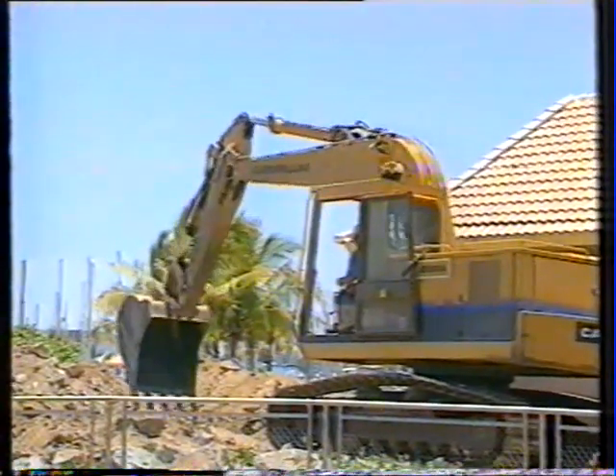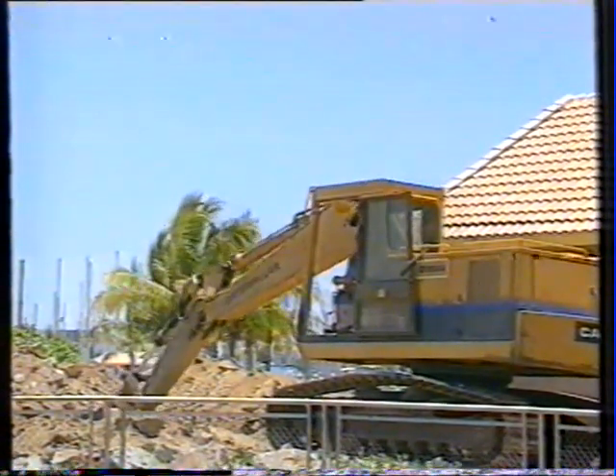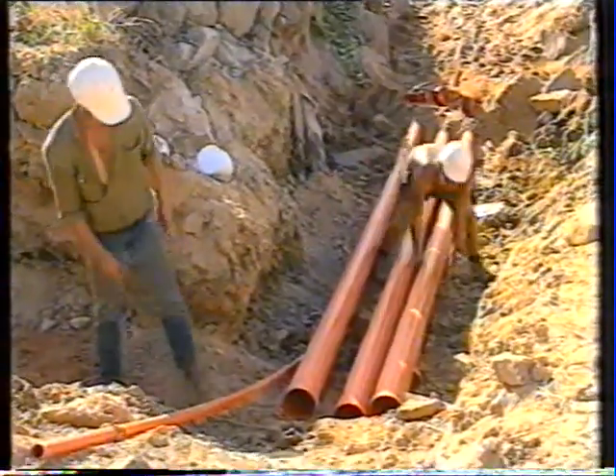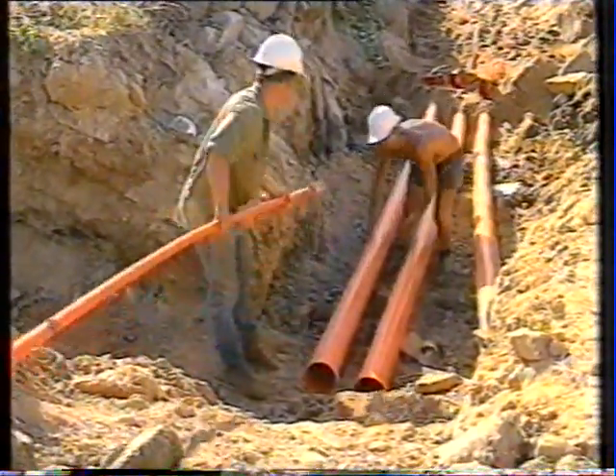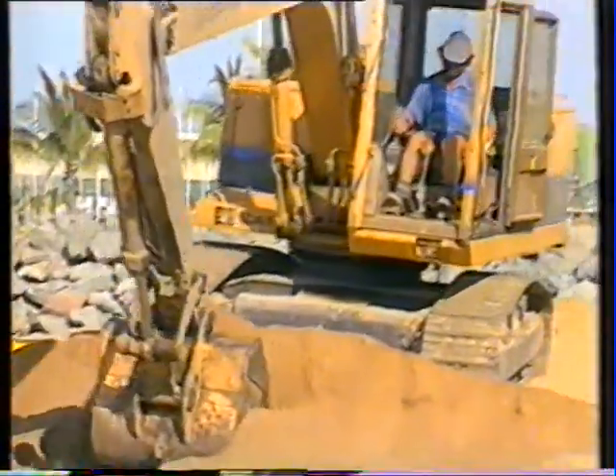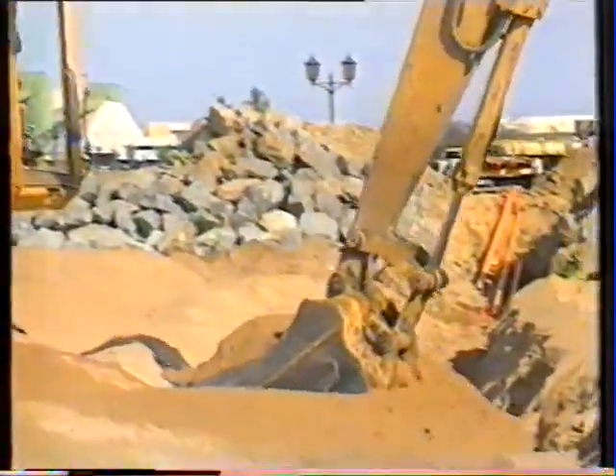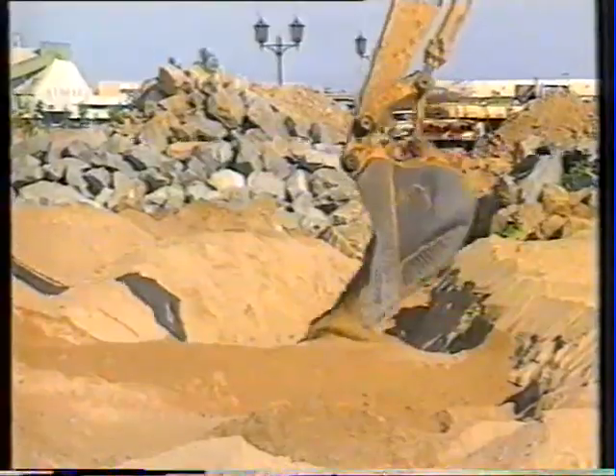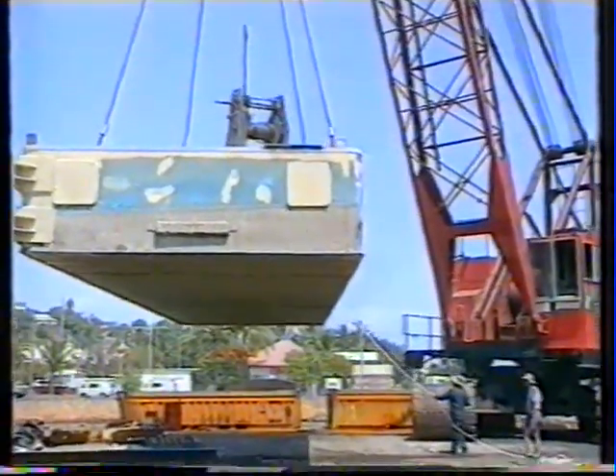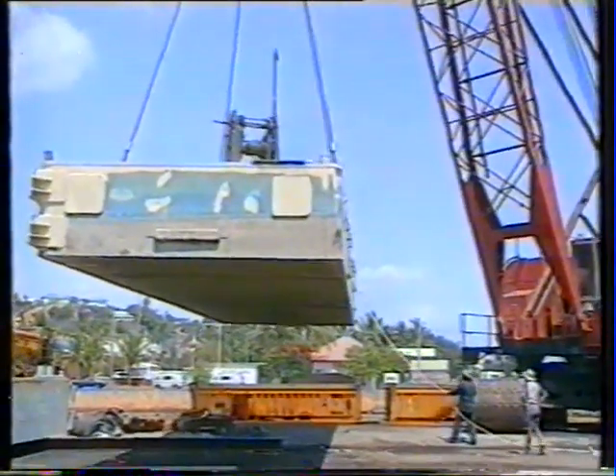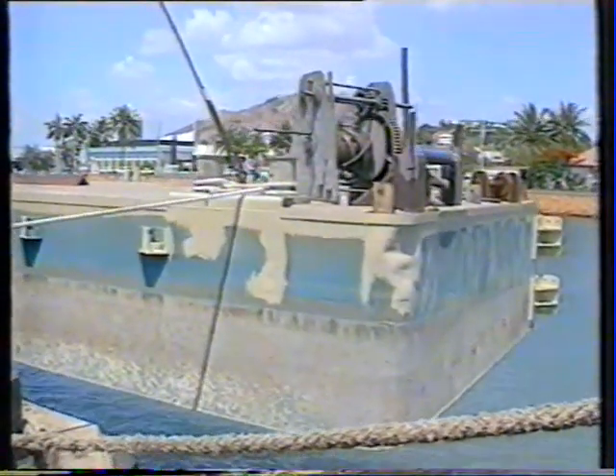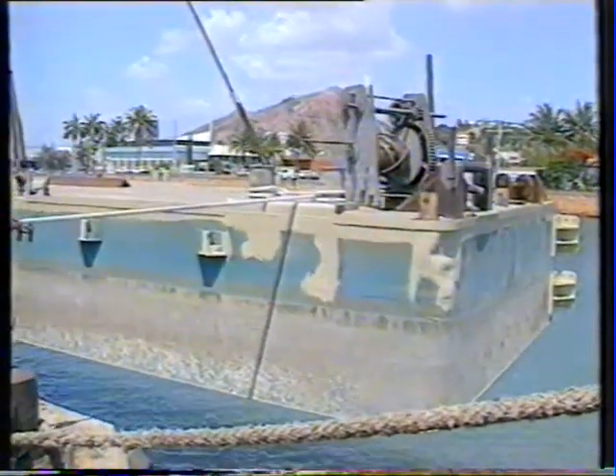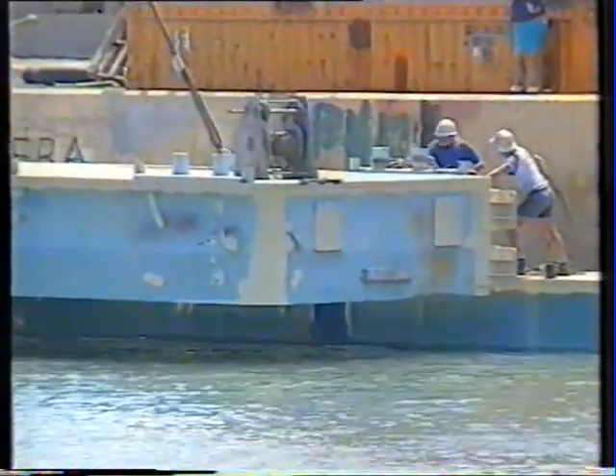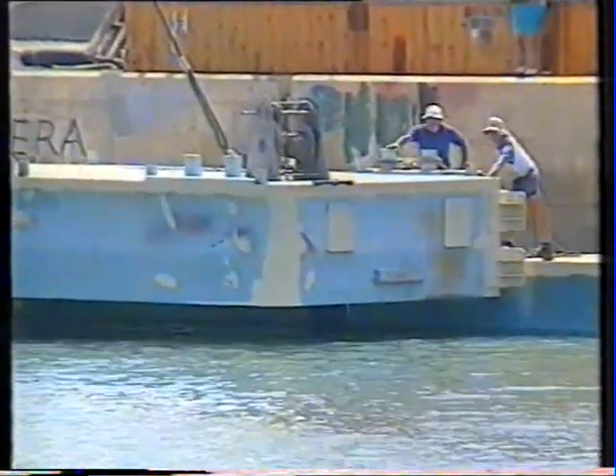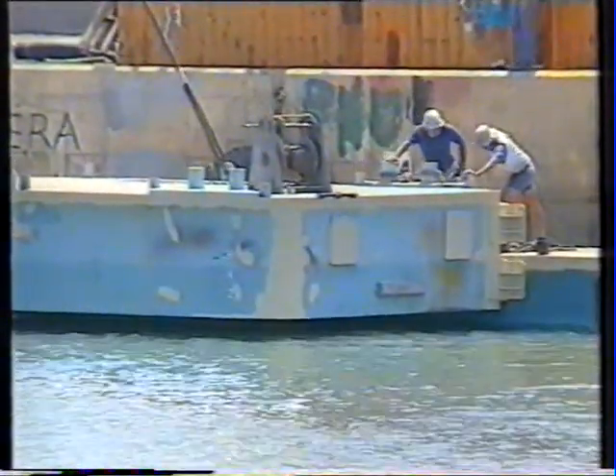Meanwhile, at the Marina end of the operation, cable ducting and excavation are proceeding above the waterline. Additional ducting is being installed in the trench to obviate any need to dismantle the rock seawall in the future. At this time, CB Marine are making preparations for the floating platform to be used by the cable jointers. The dumb barge is fitted to suit this particular job with heavy winches and 4-point anchoring capabilities. 2 of these sections will be bolted together and an air-conditioned aluminium shelter erected on the platform.